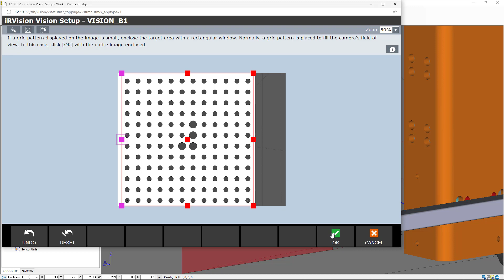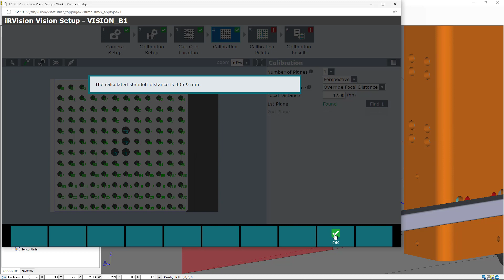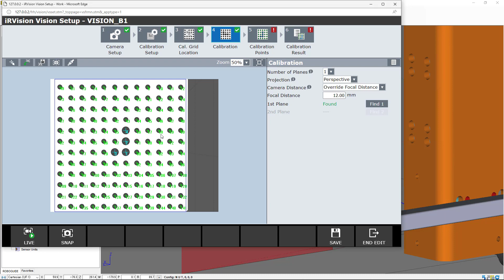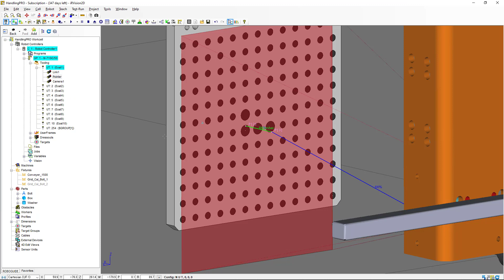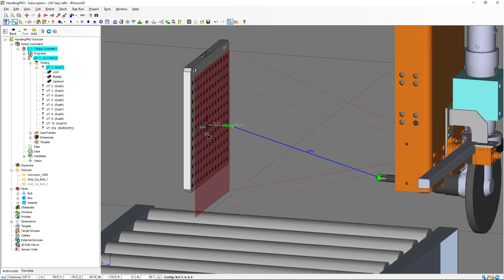You don't want to include any more points that don't belong to the calibration grid, because otherwise the calibration grid is not going to be good. So we're going to press OK, and this is telling us the calculated standoff distance is 405.9 millimeters. Okay. So this standoff distance is the distance that we have from the calibration grid to the actual camera. So again, we can measure the distance, and you need to verify that the distance calculated for the calibration is the same as the physical distance that you have on your system.